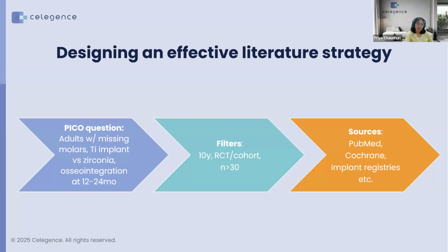Right, so we won't spend much time on this slide, but I want to highlight one key point under EU MDR, especially for legacy dental devices. Literature is often the only viable source of clinical data. So a robust clinical search strategy becomes the primary tool to demonstrate safety, performance, and the state of the art, particularly when equivalence is no longer accepted or when we do not have our own clinical investigation. So that's why building a correct search strategy matters.